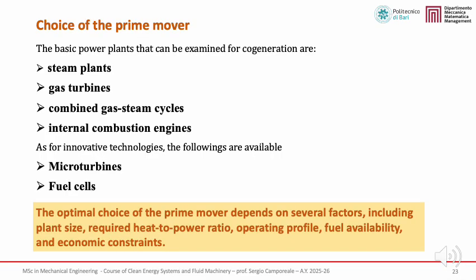In this slide, we introduce the choice of the prime mover for cogeneration applications. The selection of the prime mover is a key design decision. The choice depends on key parameters: size, heat-to-power ratio, operating flexibility, fuel type. Among conventional technologies, several power plants can be used for cogeneration. Steam plants are typically adopted in large-scale industrial applications where high-temperature heat demand is available. Gas turbines are widely used in medium to large-scale CHP systems, particularly when high-quality exhaust heat can be recovered.